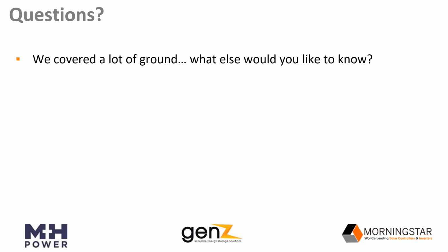Question coming in from Fabio. Question is, what is the surge current that the 48-volt genZ battery can provide, and for how long? So that would be for Albert also. Yep, Fabio, thanks for the question. So the surge current for our 48-volt is actually limited by the circuit breaker, which is 60 amp. So that is the surge current per rack-mount module of our 48-volt genZ. Okay, terrific. That answers that.